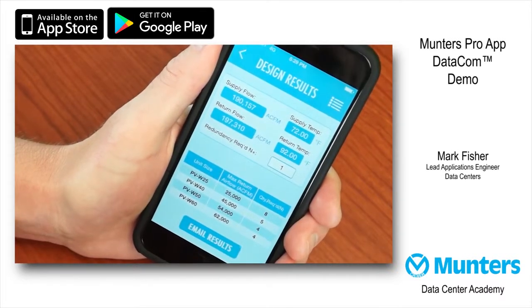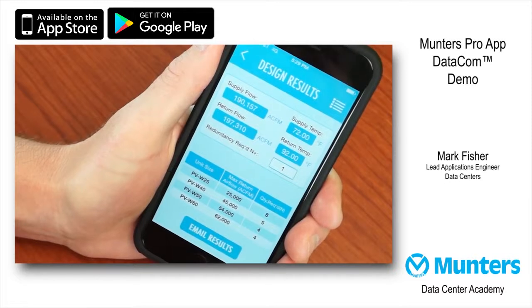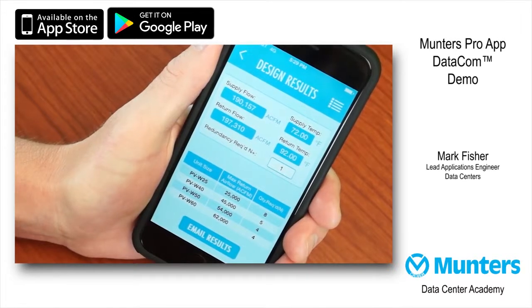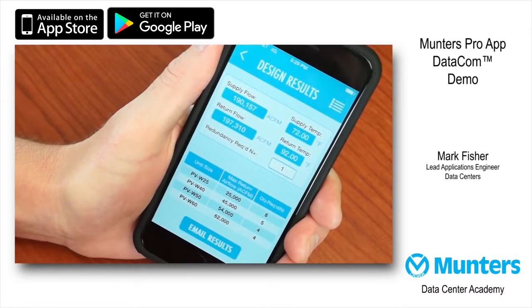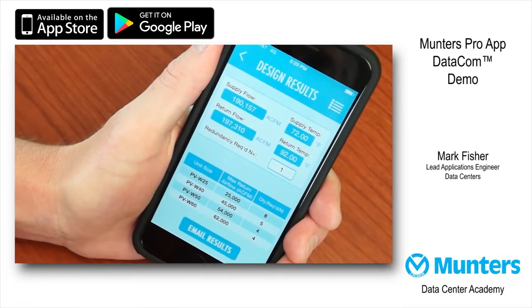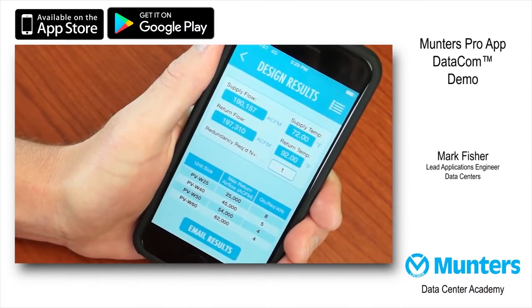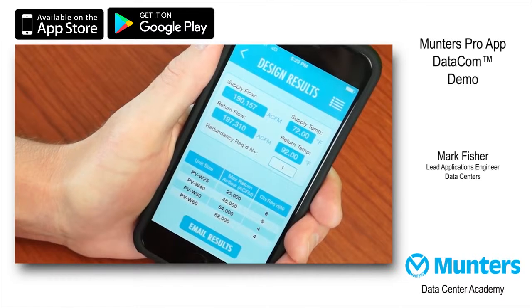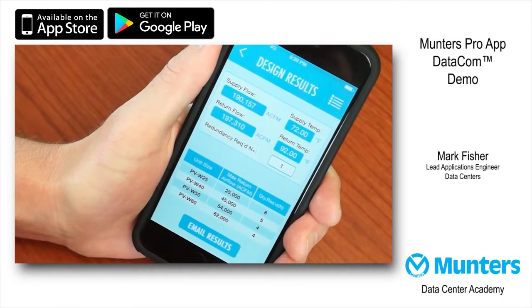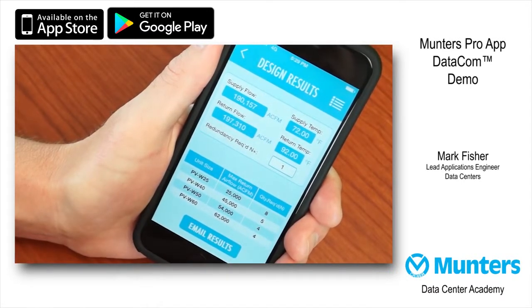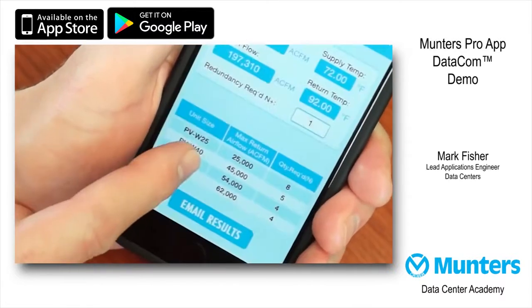So the app is telling me that for this 1.2 megawatt data center, I need 190,157 actual CFM at the supply temperature of 72, and that my return airflow is 197,310 actual CFM at 92 degrees. Munters has several standard sizes for data center equipment, and the app breaks down how many of each size unit would be required for this particular data center. In this case, I could use 5 W40s or 4 W50s to meet the load requirement.